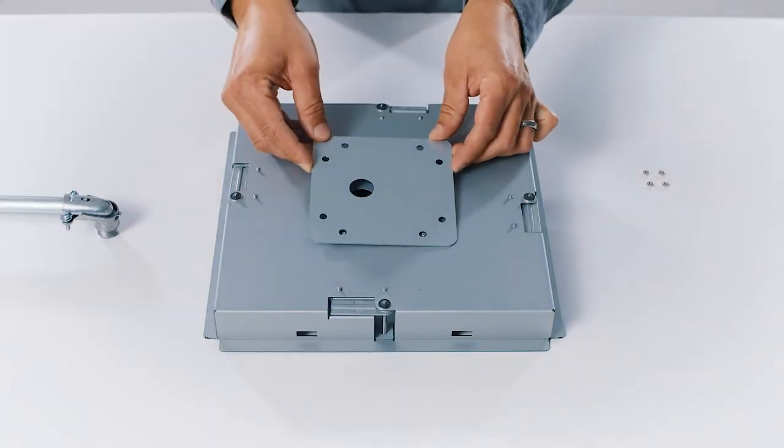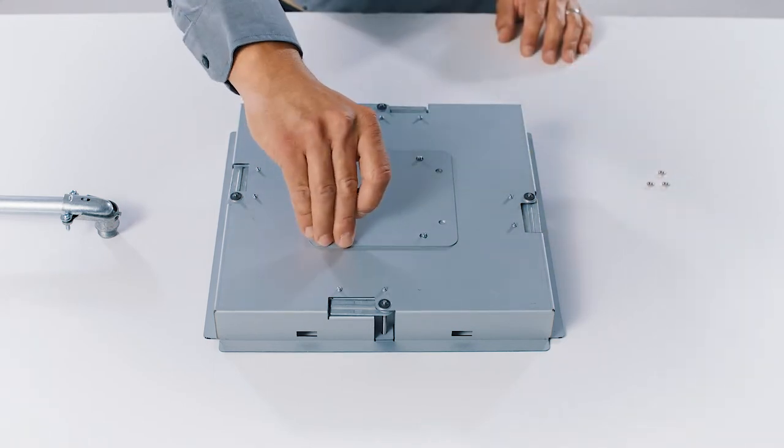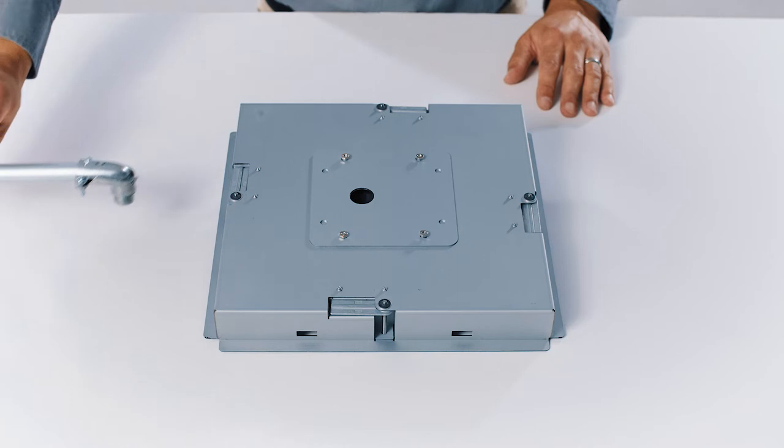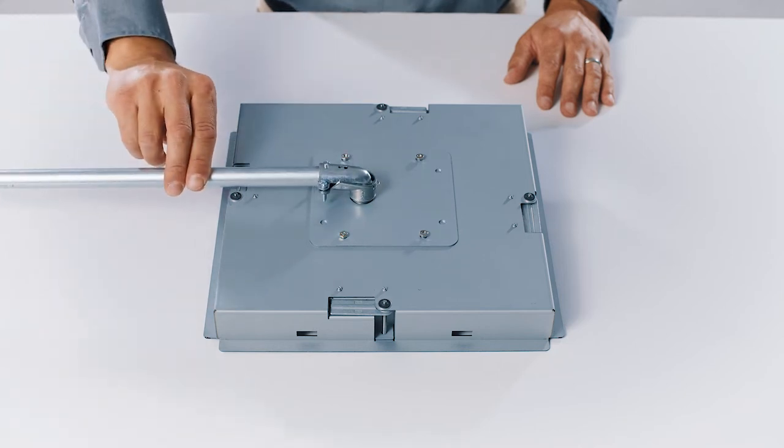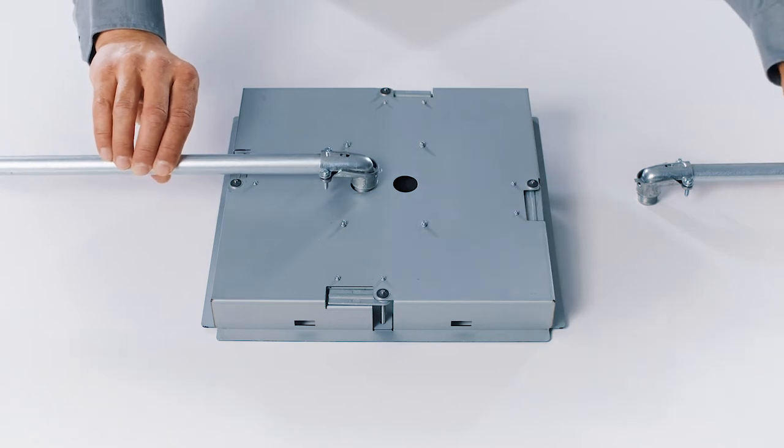The mount and hardware are UL 2043 compliant, allowing for installation in a plenum space according to most building codes. In most cases, conduit connections, not provided, should be used to meet local building codes.